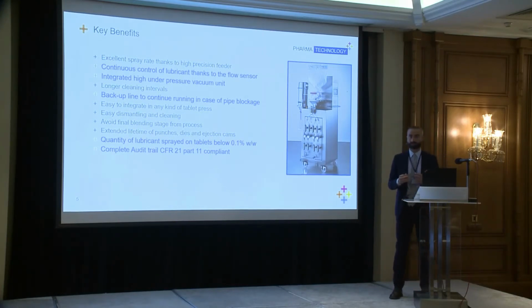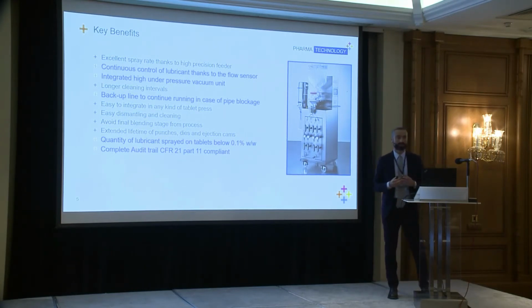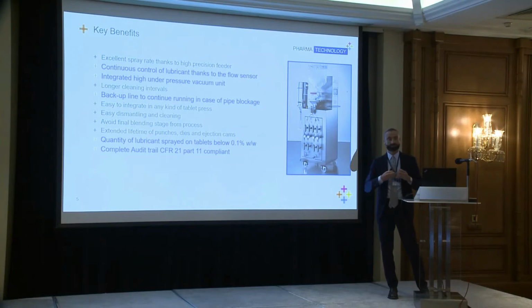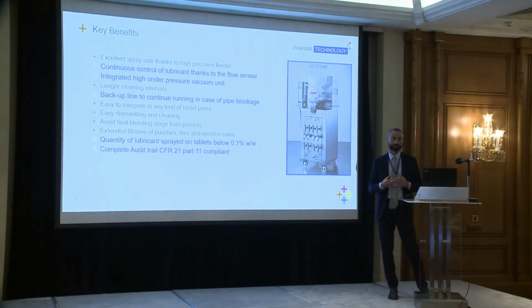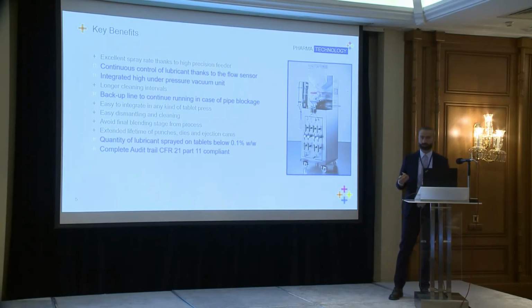What happened is that because magnesium stearate tends to bridge a lot, it's very volatile and very sensitive to static. For a few seconds we didn't spray because there was a jam inside the tube. That was enough for the tablet press to get stuck with the sticky product, and it took three hours to clean, so production was lost. So we added the flow sensor, and when the sensor detects reduced flow, we stop the press, since that means something is going on.